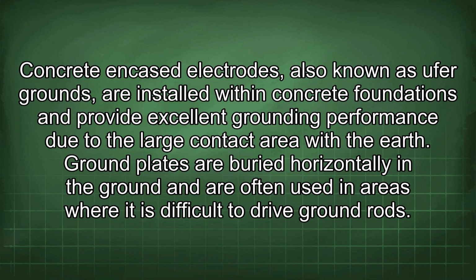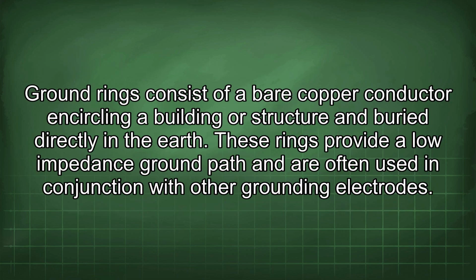Concrete encased electrodes, also known as UFER grounds, are installed within concrete foundations and provide excellent grounding performance due to the large contact area with the earth. Ground plates are buried horizontally in the ground and are often used in areas where it is difficult to drive ground rods. Ground rings consist of a bare copper conductor encircling a building or structure and buried directly in the earth. These rings provide a low-impedance ground path and are often used in conjunction with other grounding electrodes.